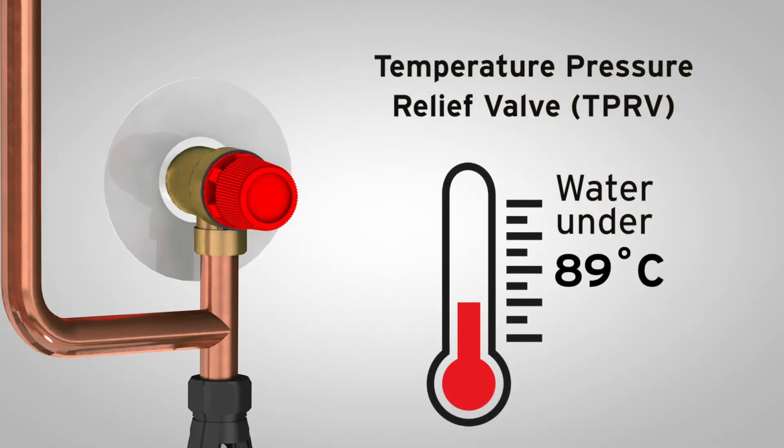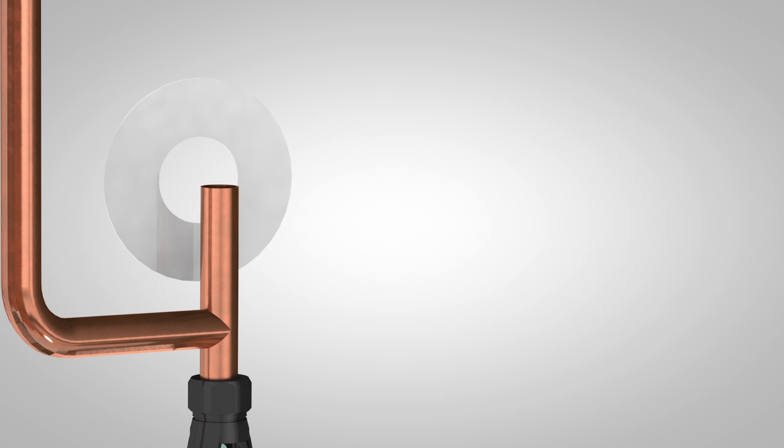If it's the temperature pressure relief valve, test the water temperature. Is it under 89 degrees? Then the valve is faulty and should be replaced.